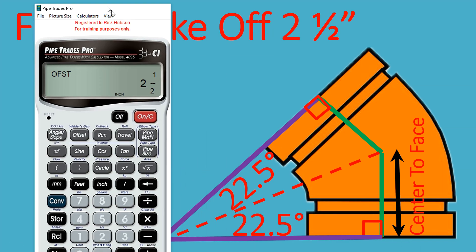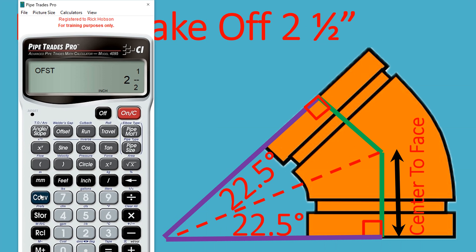So if we take our Pipe Trades Pro and we convert clear, we can put 6 inches in as the run. 22.5 is the angle slope. When we press the offset, we get 2.5 inches. Keep in mind, we had one side, one angle, enabling us to find all the sides and all the angles in that triangle.